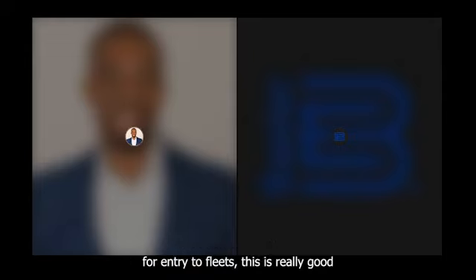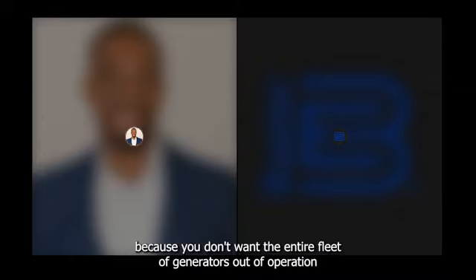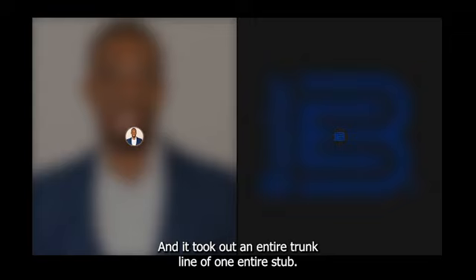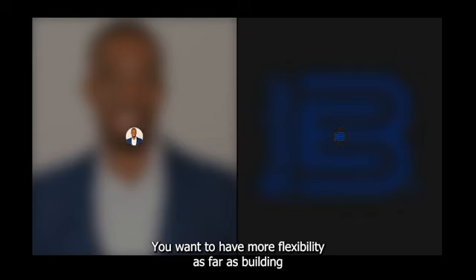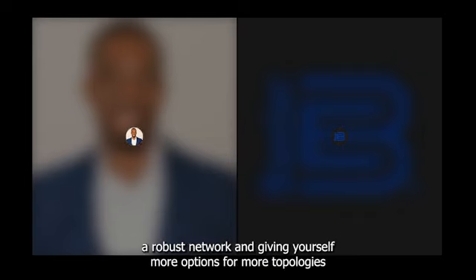And for generator fleets, this is really good because you don't want the entire fleet of generators out of operation because one node is lost, or because of something that happened on a CAN bus network and it took out an entire trunk line or an entire stub. You want more flexibility in building a robust network, more options for topologies, and the ability to reconfigure in ways that limit risk to the network. So: faster transmission rates, more topologies, lower risk of failure, redundant communications, and the ability to be plug and play.